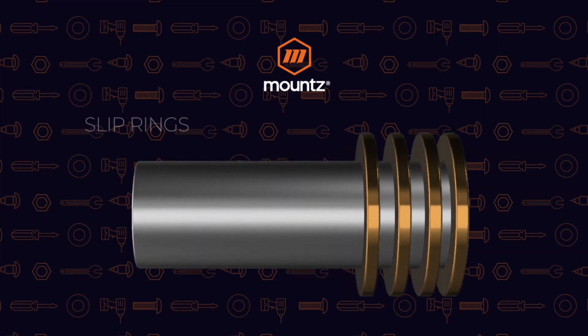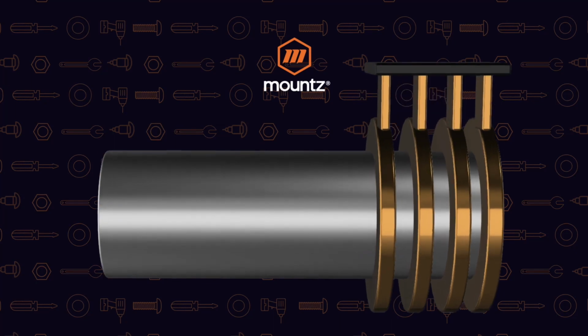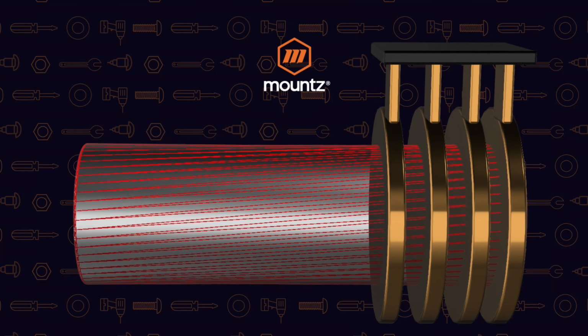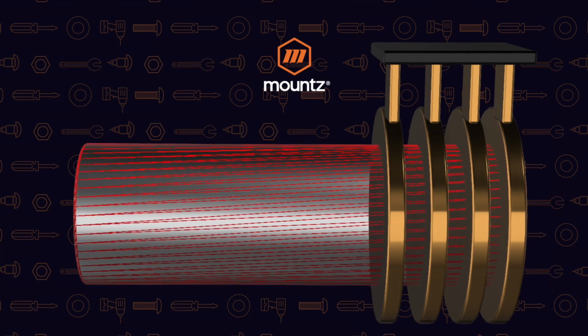For the rotary sensor, the strain gauge is monitored through slip rings, and we're measuring at different points through those rings what the actual resistance is as the shaft is rotating. So it's a little different than the reaction style transducer, but again we're measuring the resistance happening through the circuit. Often, if a sensor gets applied with too much torque outside of its range, you get an over-torque situation where there might be an offset you'd see, because the gauge has been applied with so much torsion that it ends up breaking that little sensor.